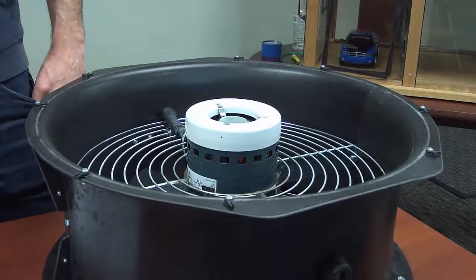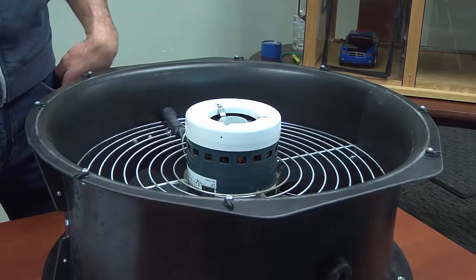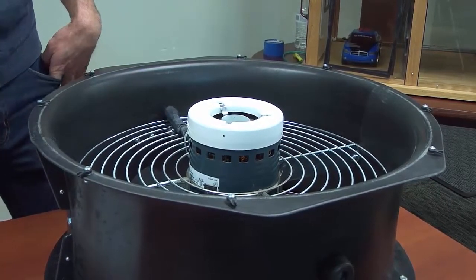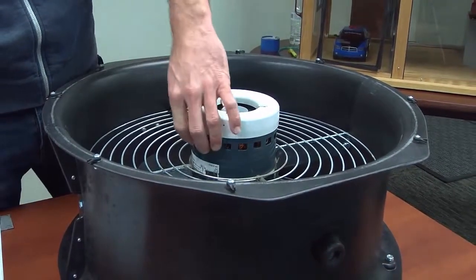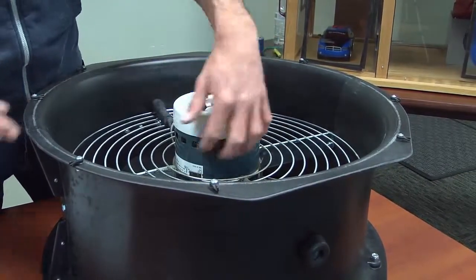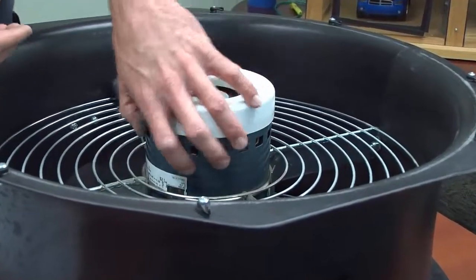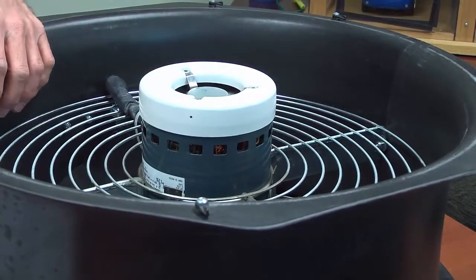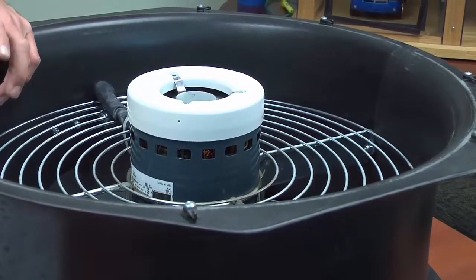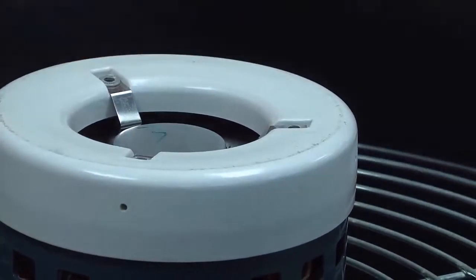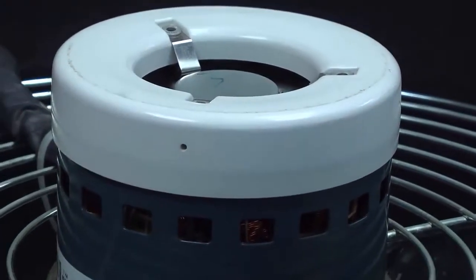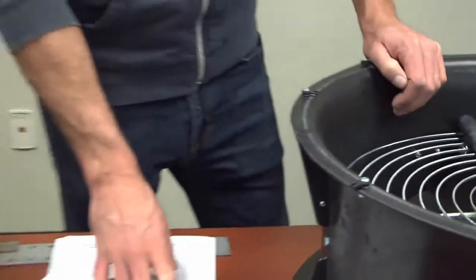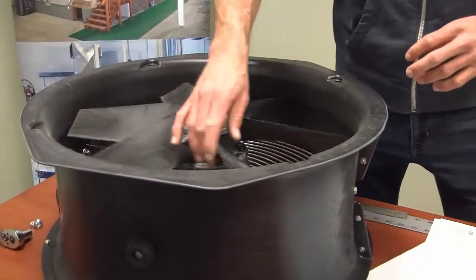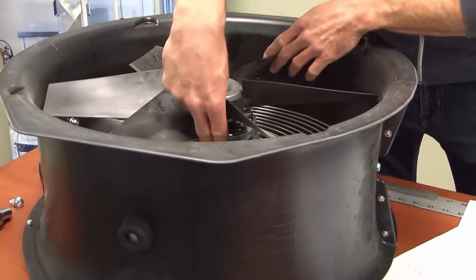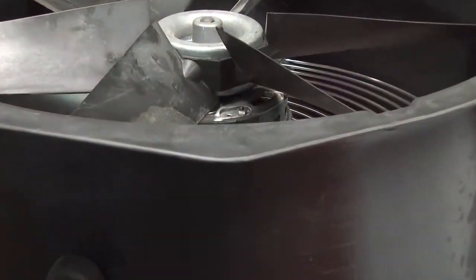All right, so some general maintenance items in regards to our blower doors. You want to examine the motor cooling holes around the exterior of the motor and make sure they're not all clogged up with dust. You could either use a vacuum with a brush or compressed air and blow those out to make sure that motor can cool off. That's not going to get too hot while you're operating it. And this is the back side, and then you got this side over here. You can see it's got holes on both sides of the motor.